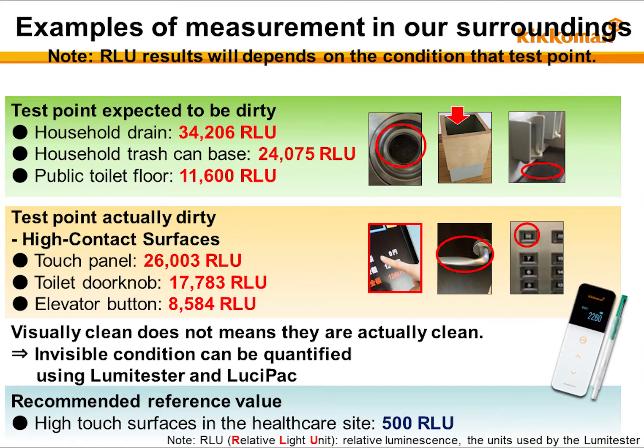Here you can see examples of measurements in our surroundings with the Lumitester and LuciPac. Measurements of locations that are generally considered to be contaminated may show values of 10,000 or more. High-touch surfaces frequently contacted by many people can be just as dirty, and Lumitester measurement values confirm this even if the area seems visually clean. High Lumitester values mean that soil and dirt still remain on that test point. For infection prevention and control in hospitals, results of environmental hygiene after cleaning are recommended to be 500 RLU or less when measured with the Lumitester.